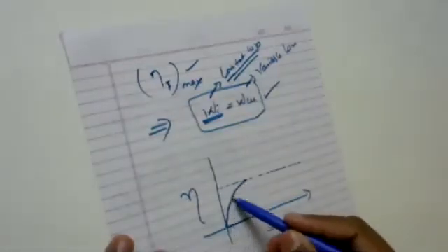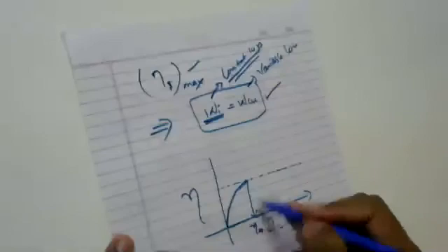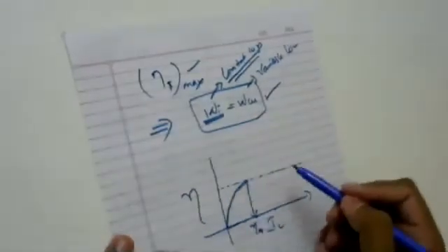The moment the variable loss becomes equal to the constant loss, this is the point where you get maximum efficiency. Your efficiency will not go beyond this. If you operate your transformer beyond this point, it is called overload. This is the maximum your transformer can give. But if you still go on loading your transformer, then your efficiency will start dropping.